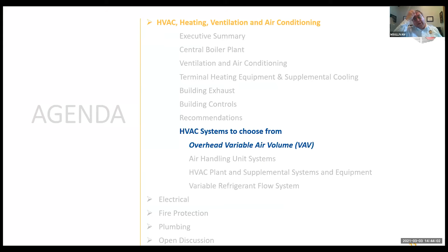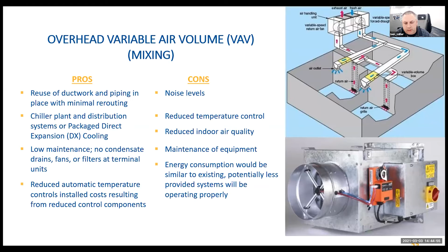Overhead variable air volume mixing boxes, the pros would be reuse of existing ductwork and piping in place with minimal rerouting, chiller plant and distribution systems, or package direct expansion cooling, low maintenance, no condensate drains, fans, filters at the terminal units, reduced automatic temperature controls installed costs resulting from reduced control components, again because most of those are probably already in place. The cons would be noise level, reduced temperature controls, reduced indoor air quality, maintenance of equipment, energy consumption will be similar to the existing building, potentially less, providing systems will be operating properly.